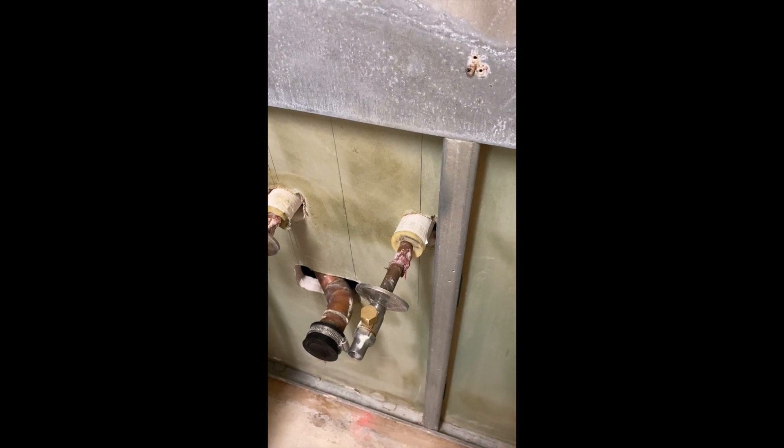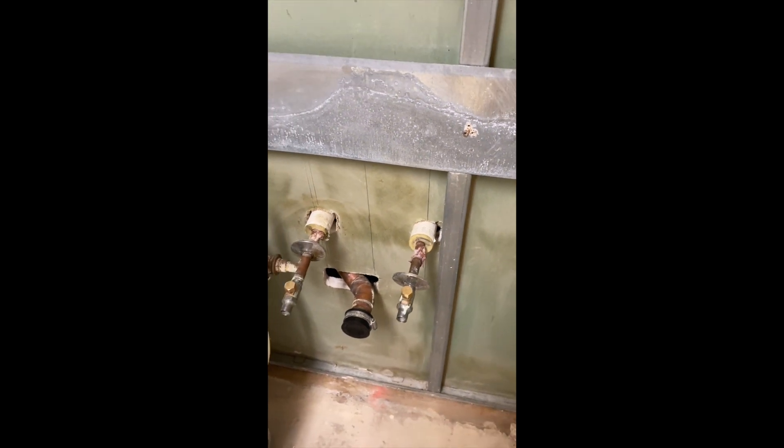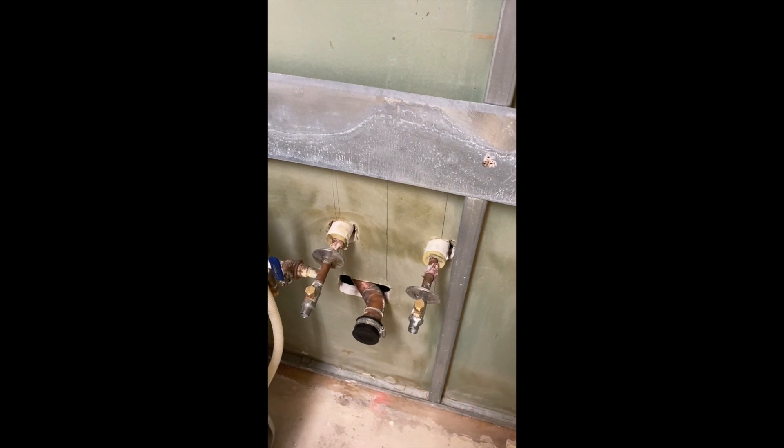This unfortunately is a common occurrence, even in construction I see today — somehow people neglect the shaft liner side. And this is a massive problem because a shaft is an opportunity. If a fire gets inside, it can access every single floor that that shaft wall passes through.